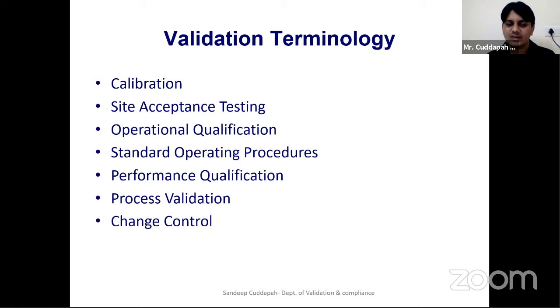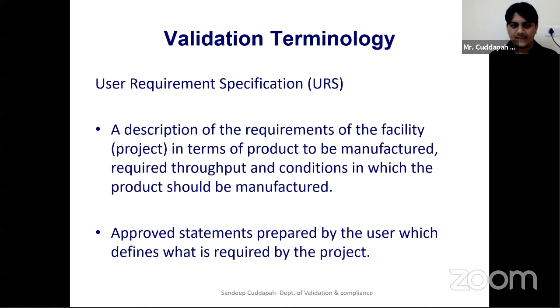Then lastly, change control comes into the picture. As I told you, if the equipment settings do not meet your process, you will raise a change control and change the settings in the performance qualification. Based on the criticality of the change control, you will decide whether you have to repeat the performance qualification or can fine tune the settings and perform the process validation. Then I'll brief you regarding user requirement specifications. It is actually a description of requirements.